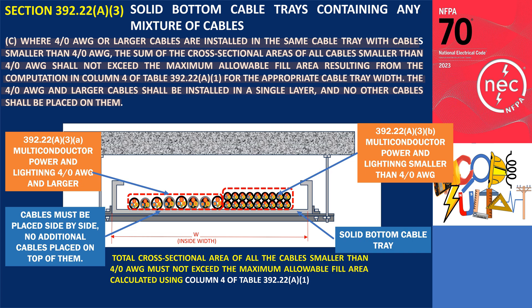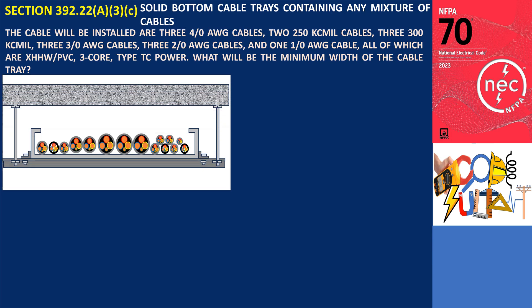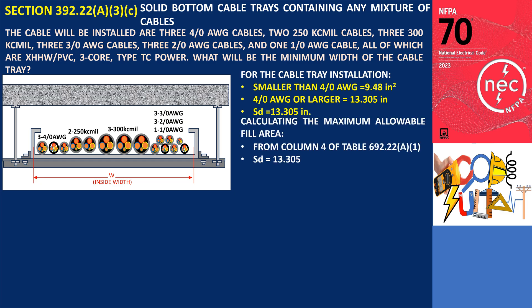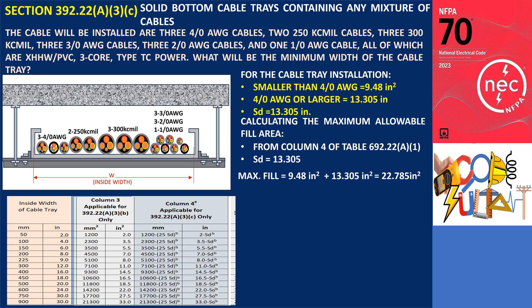To understand this, let's combine the two previous examples. Since we calculated the total width of the 4-aught AWG and larger cables and the total cross-sectional area of multi-conductor cables smaller than 4-aught AWG, we can now determine the minimum inside width of the cable tray. Cables smaller than 4-aught AWG have a total cross-sectional area of 9.48 square inches. For cables that are 4-aught AWG or larger, the total overall diameter is 13.305 inches, which we designate as SD as per Column 4 of the table. Adding the 9.48 square inches from the smaller cables to SD, the total fill area comes to 13.305 plus 9.48, equaling 22.785 square inches.